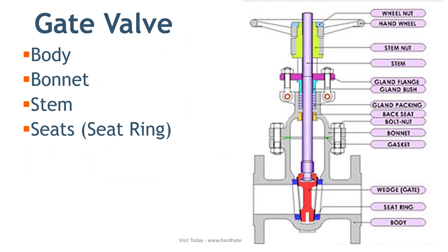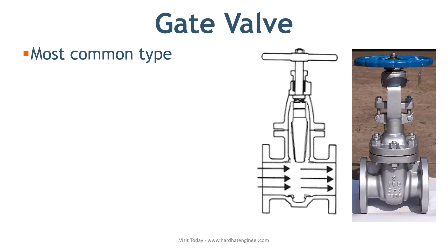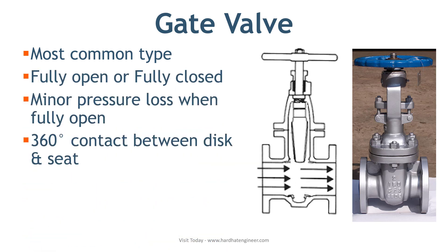On this slide, you can see the section drawing of a gate valve which shows the parts of the gate valve. It consists of a body, bonnet, disc, stem, handwheel, and other trim parts. The distinct feature of the gate valve is the sealing of the passage by the gate or wedge and seats. A gate or wedge of the gate valve moves perpendicular to the flow of the service. When you move the stem to the up position, the valve is open, and in the down position, the valve is closed. You can see the same on the slide.